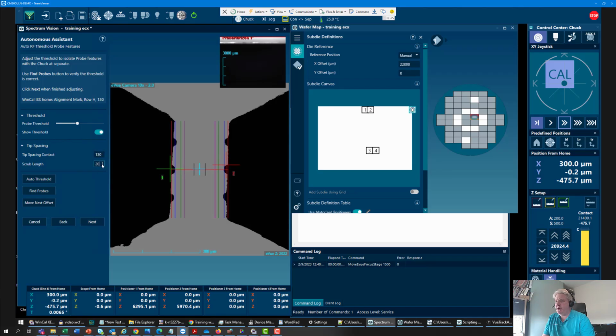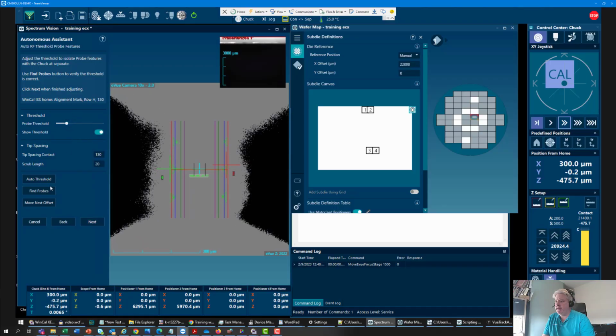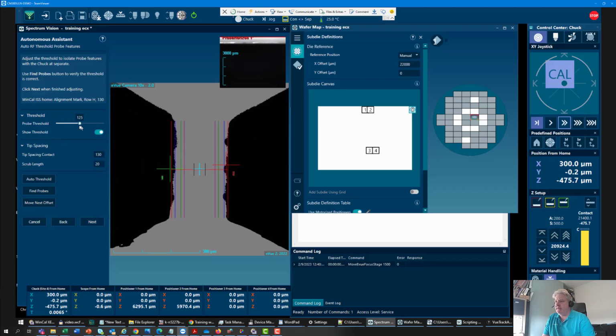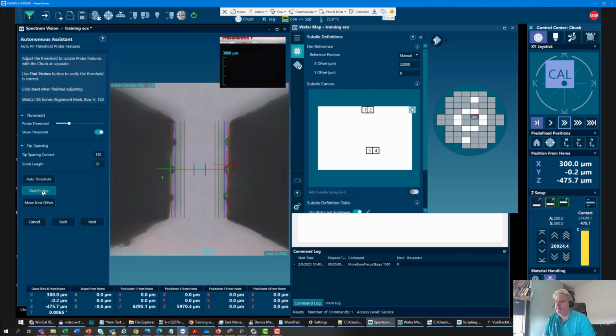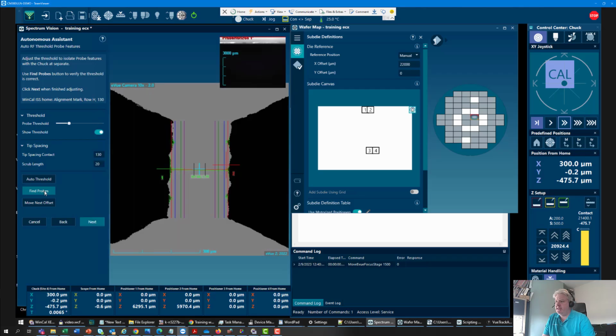So if I press find probes, you can see we're finding probe tips well. If I have this set to some value like here, you see we find nothing. It'll just be garbage. It doesn't find anything at all. If it's even close, you'll see what you can sometimes see. It will find some sort of erroneous stuff going on. Though it actually seemed to do pretty well there, but it's best to make sure the tips look nice and clean with not too much noise and sparkly bits in them. That's great.